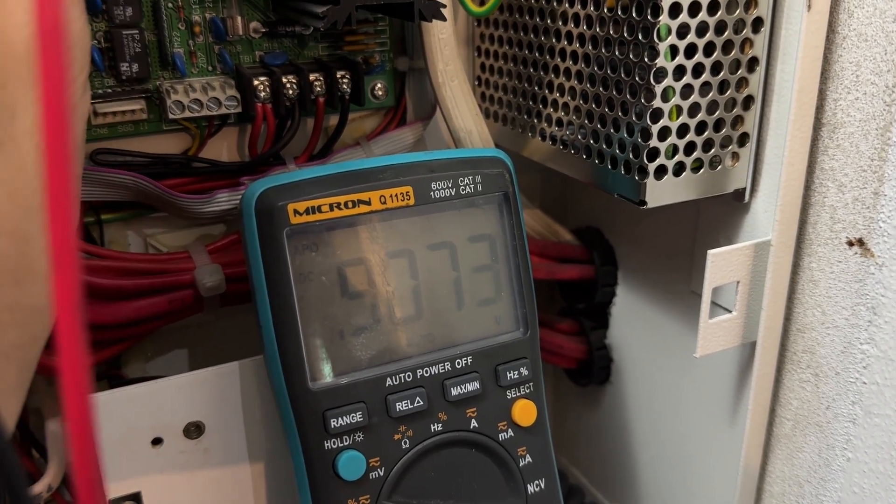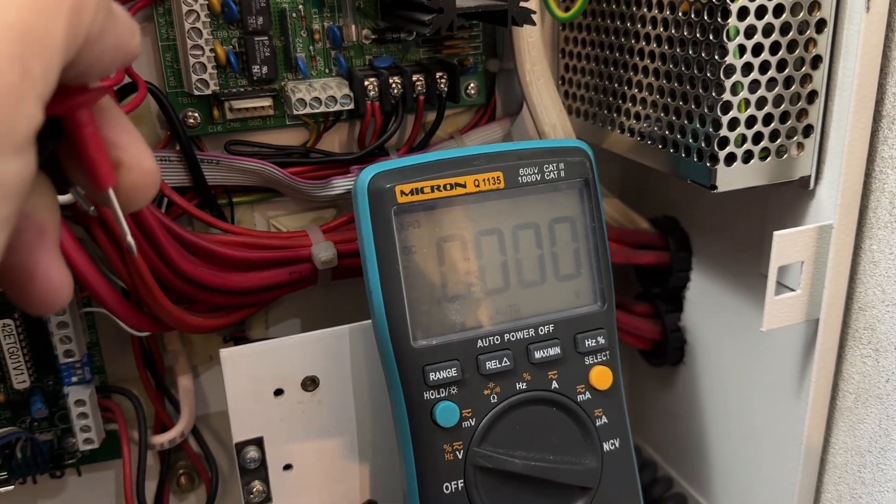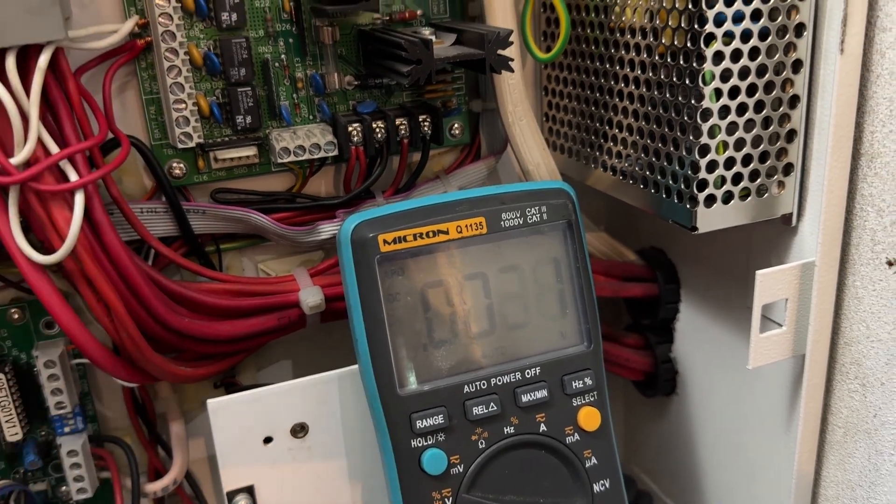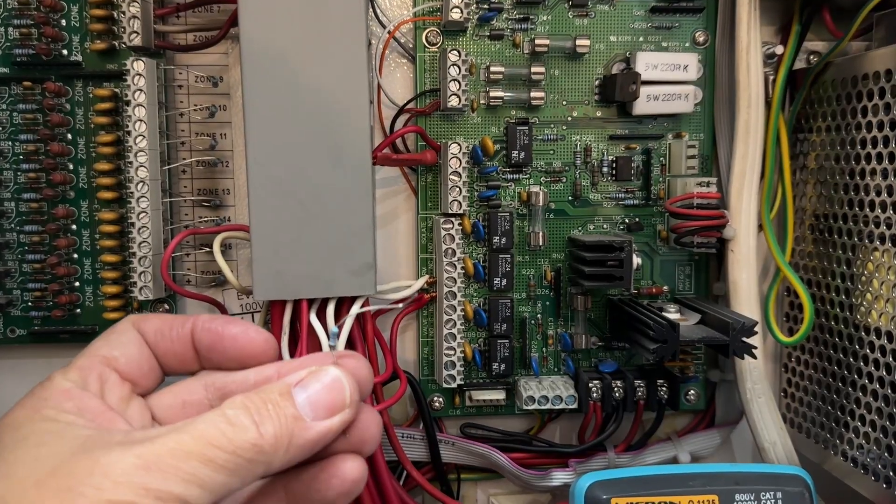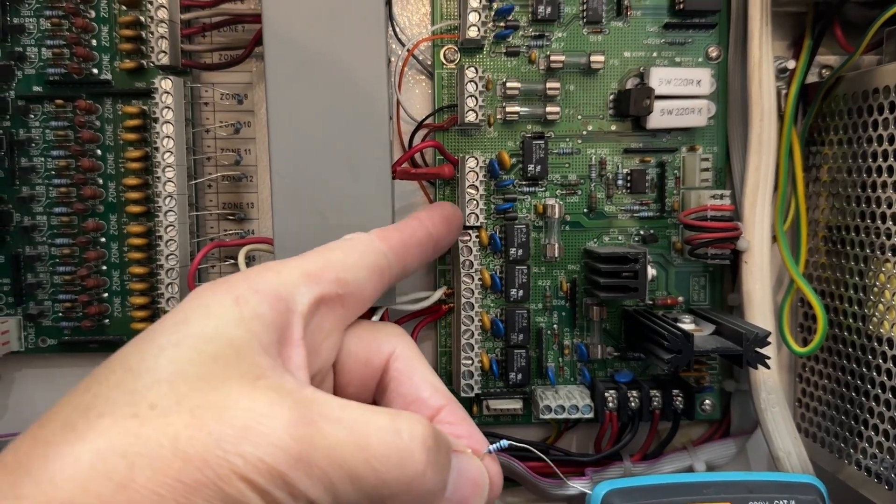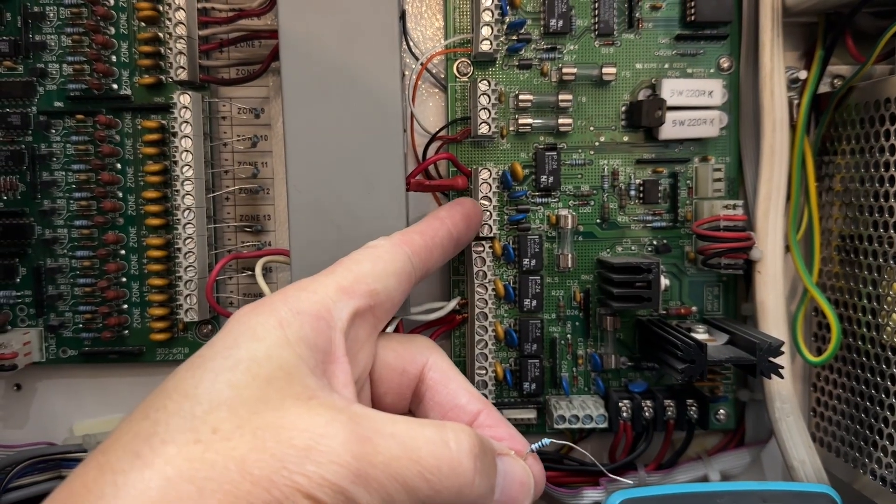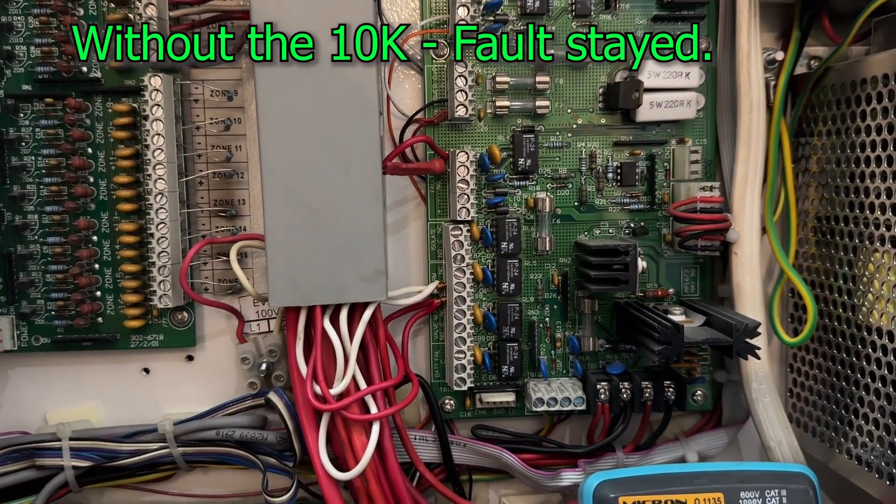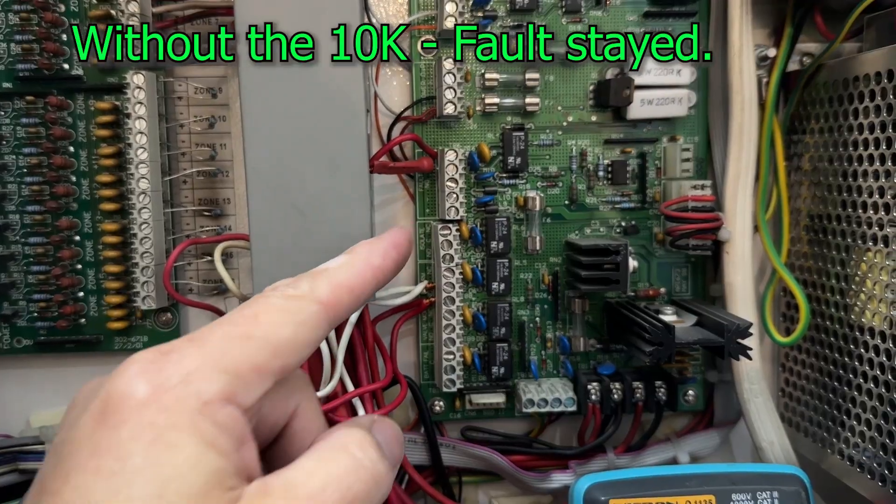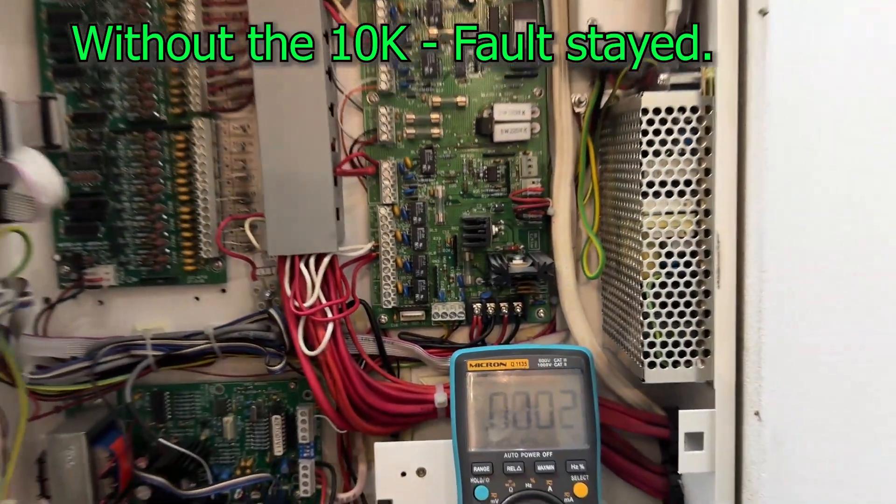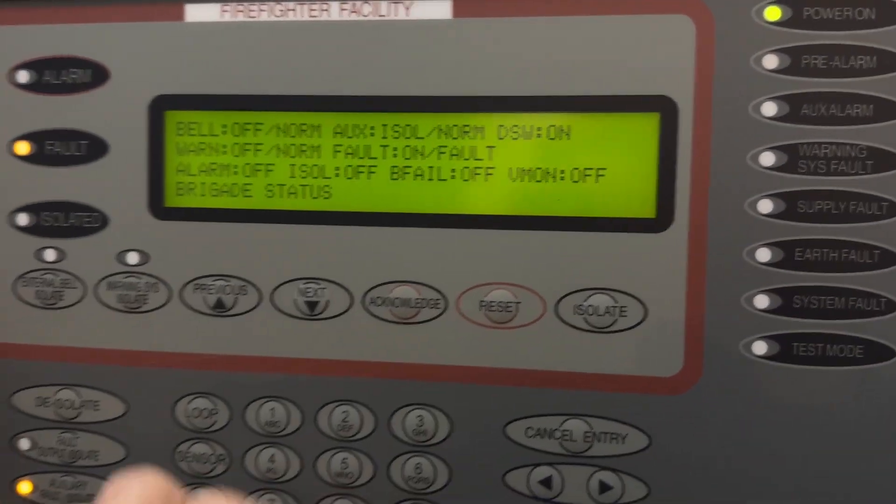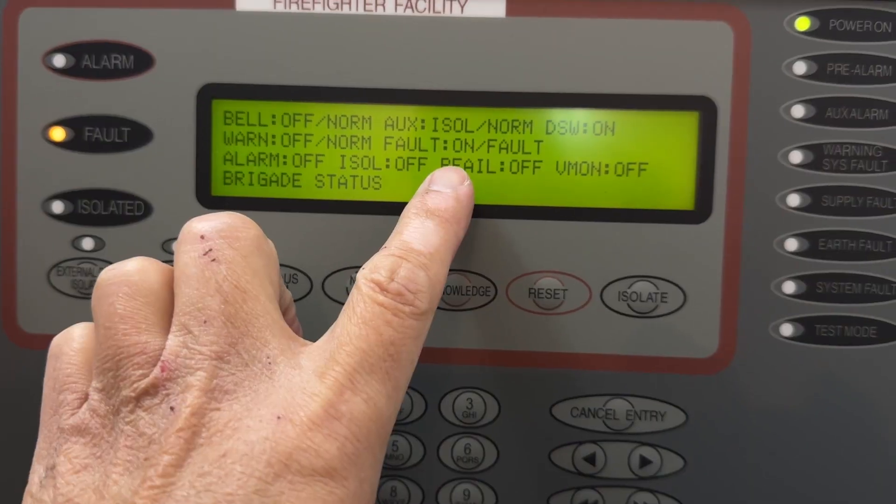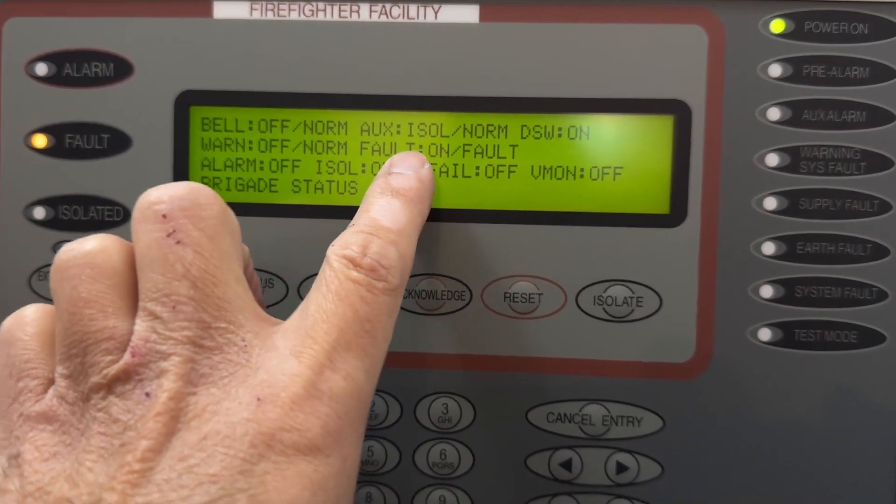I'm going to remove the resistor and let's see if the fault will stay. This is the resistor that's connected to that fault output. Now I don't hear any noise. The intermittent fault is gone. And if you will see here, see that fault is on and I have a fault on that fault relay.